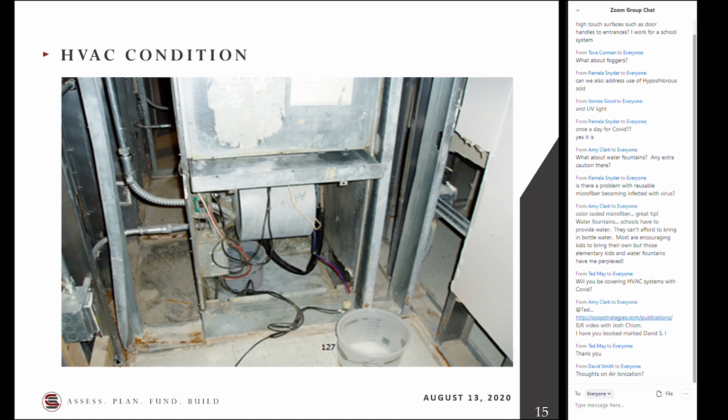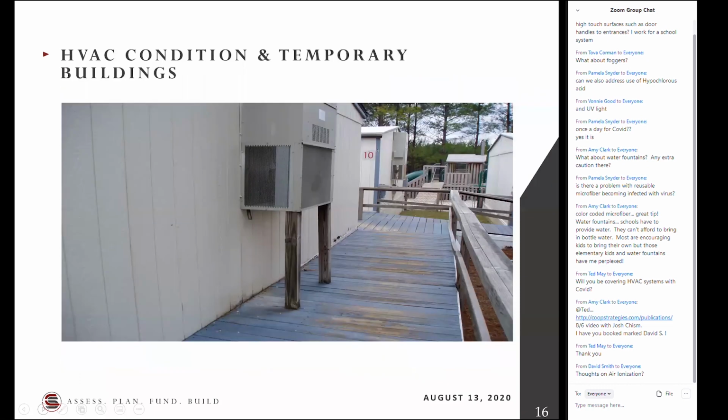That was in the wintertime. Yeah, preventative things, and that's a pretty easy fix. I guess you've got a couple more slides. I took this picture at a modular unit. They had a packaged unit on the outside, and they didn't really think about how to get rid of the condensate. There's a lot of water dripping out of those units in the summertime.